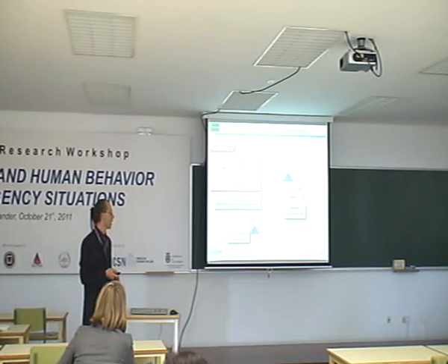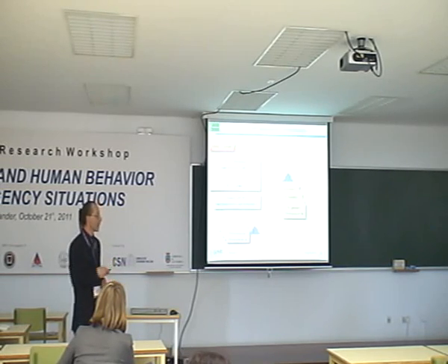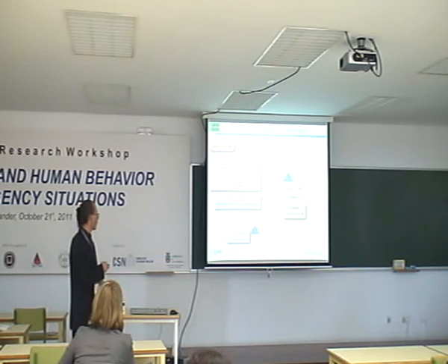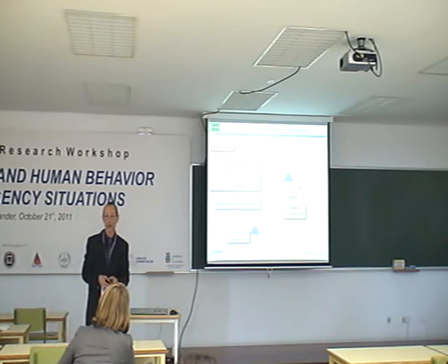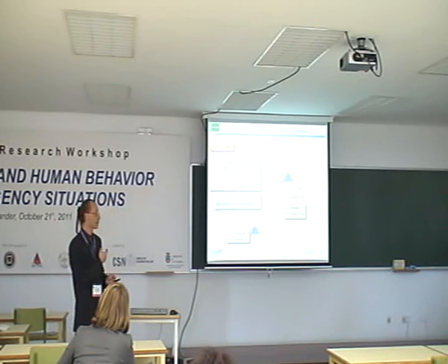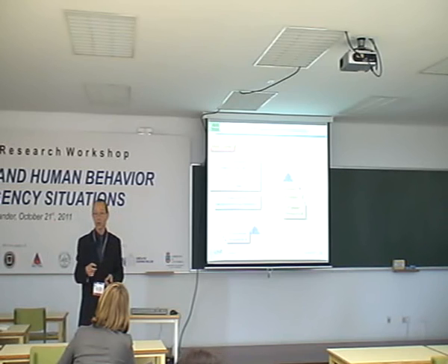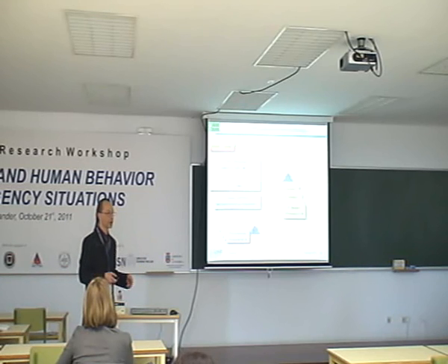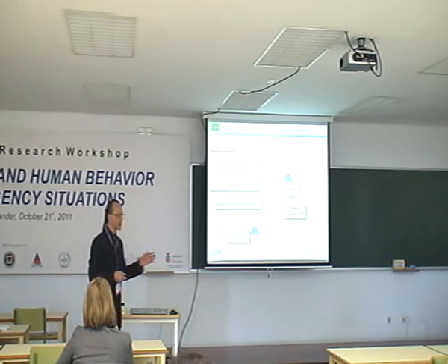on ISO 13571. And then we run thousands of evacuation scenarios, and this is maybe one of the difficult parts of this methodology, because we have to choose the population in the building as representative as it could be. I mean, here we are during a conference. People here are not the same as if there were only students, and such an evacuation part should take this into account and include some unusual population and subpopulation into this statistical approach.